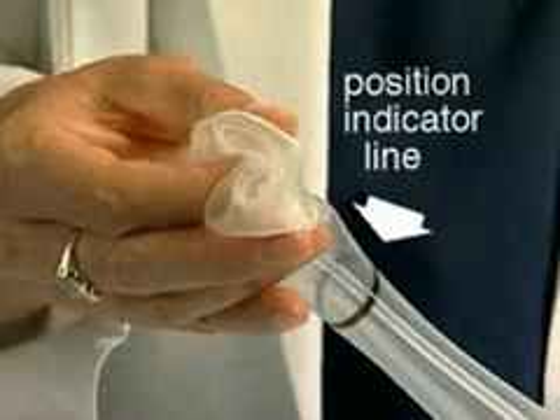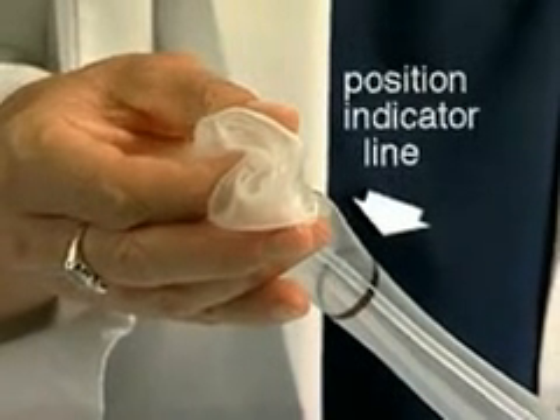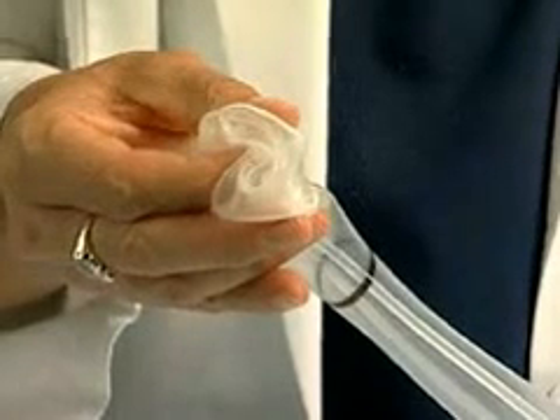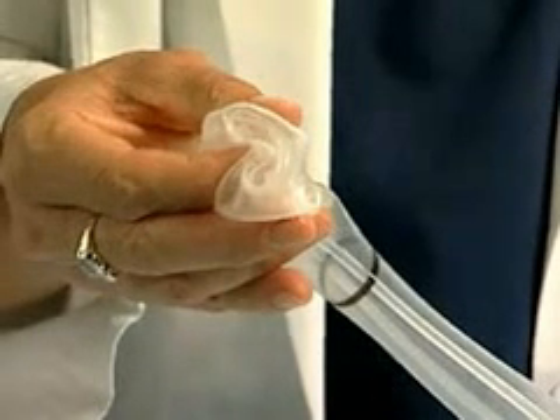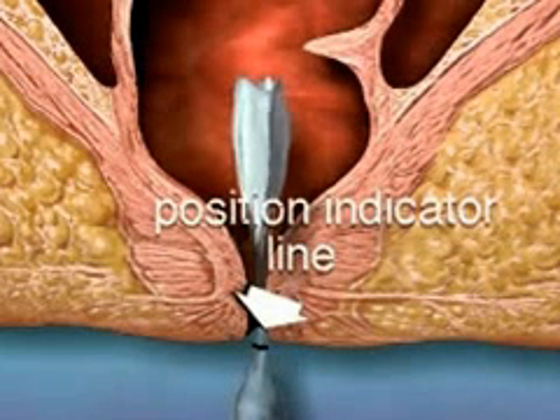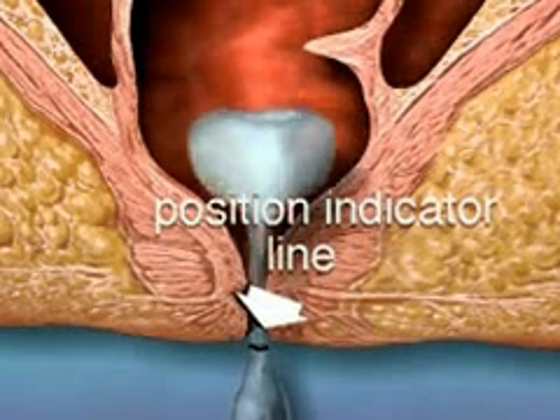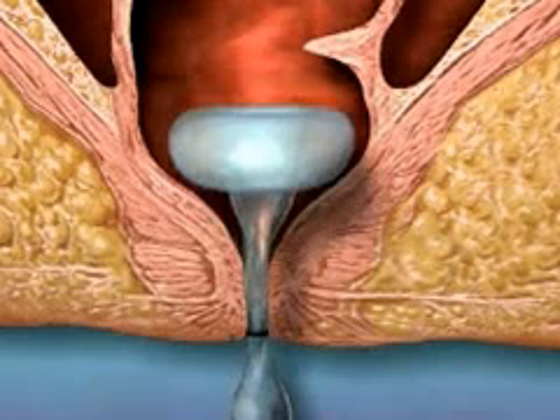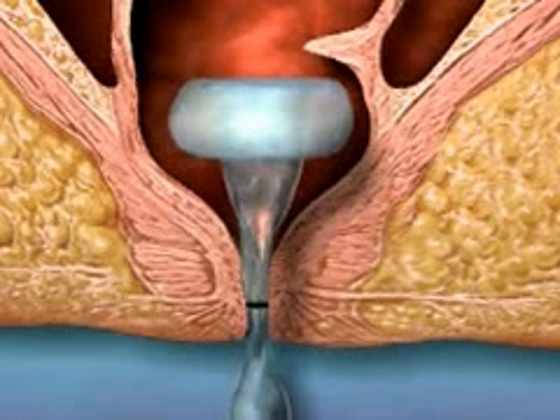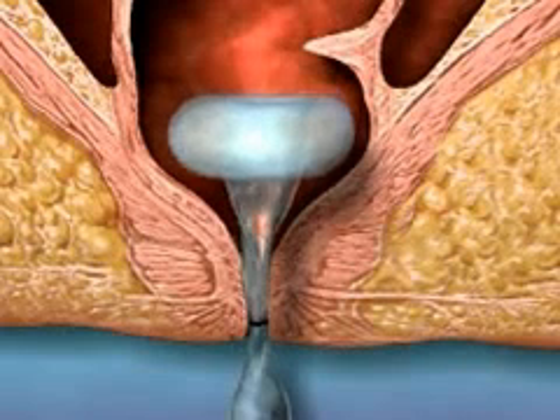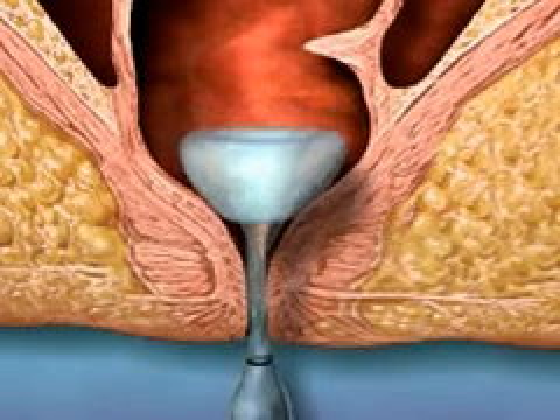You should observe changes in the location of the position indicator line as a means to determine movement of the retention balloon in the patient's rectum. This may indicate the need for the balloon or device to be repositioned. If the position indicator line moves up, that means closer to the anus, this may indicate that there is a need to gently pull the catheter to bring the balloon where it should be.